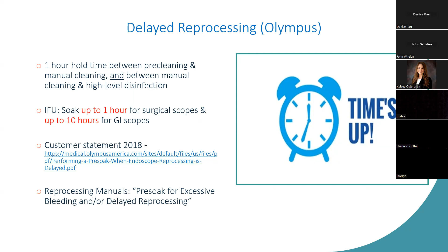So for example, Olympus calls for extended detergent soaking if there's more than 1 hour delay between pre-cleaning and manual cleaning. Currently, they have the most prescriptive direction. That's repeated in AAMI and AORN's guidance. And realize in Olympus's reference, they speak to the 1 hour between pre-cleaning and manual cleaning, but they also talk about 1 hour between manual cleaning and high-level disinfection. So if you have a facility where they're staging scopes, staging them to get cleaned and then staging them after cleaning before high-level disinfection, you need to pay attention to the clock there as well.